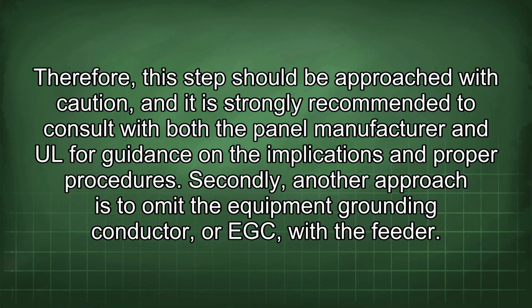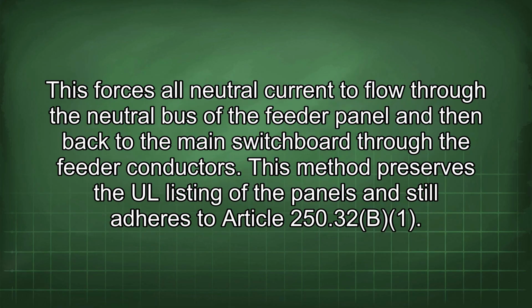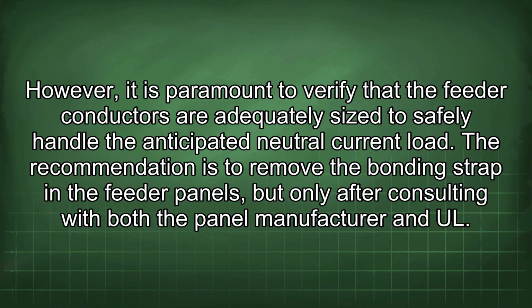Secondly, another approach is to omit the equipment grounding conductor, or EGC, with the feeder. This forces all neutral current to flow through the neutral bus of the feeder panel and then back to the main switchboard through the feeder conductors. This method preserves the UL listing of the panels and still adheres to Article 250.32. However, it is paramount to verify that the feeder conductors are adequately sized to safely handle the anticipated neutral current load.